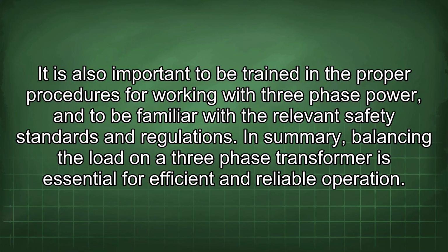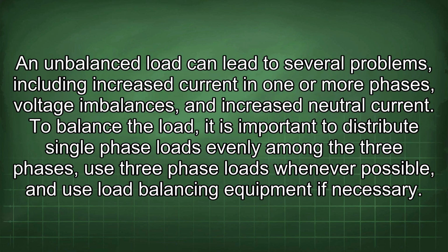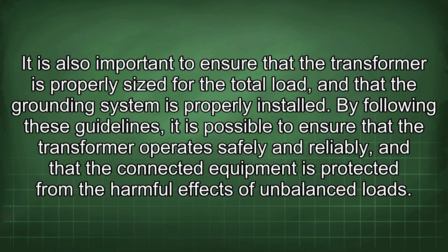In summary, balancing the load on a 3-phase transformer is essential for efficient and reliable operation. An unbalanced load can lead to several problems, including increased current in one or more phases, voltage imbalances, and increased neutral current. To balance the load, it is important to distribute single-phase loads evenly among the 3 phases, use 3-phase loads whenever possible, and use load balancing equipment if necessary. It is also important to ensure that the transformer is properly sized for the total load and that the grounding system is properly installed. By following these guidelines, it is possible to ensure that the transformer operates safely and reliably, and that the connected equipment is protected from the harmful effects of unbalanced loads.